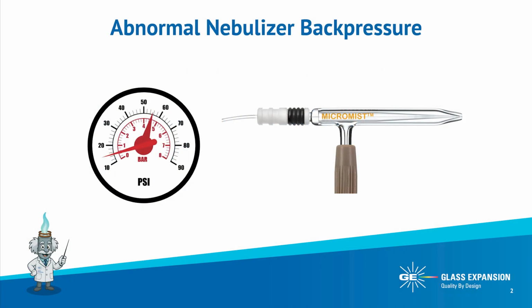Thank you and welcome everyone to Plasma Pro Tips. Plasma Professor here, and today we're focusing on nebulizer backpressure, a key indicator of system performance. Nebulizers are designed to operate within a specific pressure range, and an unusually high or low backpressure is a warning sign that something's off, and you'll need to address it before starting your analysis.